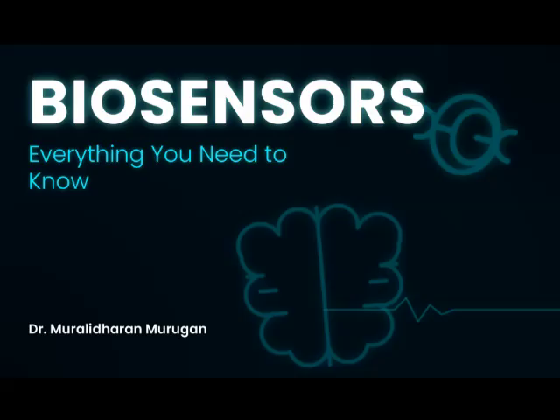You're very astute to pick up on that, absolutely. Selectivity can indeed be a challenge. Various organic compounds present in biological fluids like ascorbic acid, vitamin C, or uric acid, they can be co-oxidized at the electrode surface, producing interfering signals. False positives, essentially. Exactly. However, this is ingeniously mitigated by using specific semi-permeable membranes, such as those made from cellulose acetate or cellulose nitrate. These membranes act as molecular sieves, basically. They allow only the analyte and reaction products to pass through, effectively blocking larger interfering molecules. Like a tiny filter. Precisely. Another strategy is to perform differential measurements. You compare the signal from the sensor with the active enzyme to a control signal from a similar sensor without the enzyme.